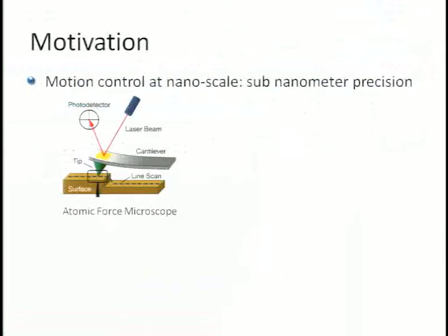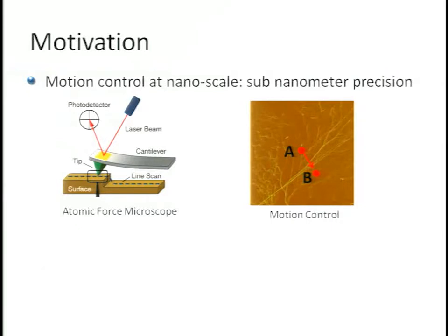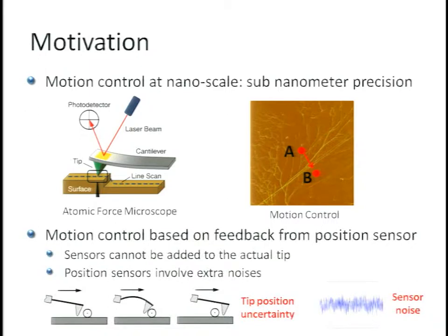Recently, atomic force microscope, or AFM, has been widely used to manipulate nanostructures. The fundamental requirement for such nano manipulations is to move the tip position from one point to another. In applications such as DNA manipulations, it is critical to achieve sub-nanometer accuracy. For nanoscale motion control, most methods rely on feedback from position sensors, but sensors can only be added to piezo actuators instead of the actual tip. Meanwhile, sensor noise at the nanoscale prevents the sensor from providing accurate feedback.